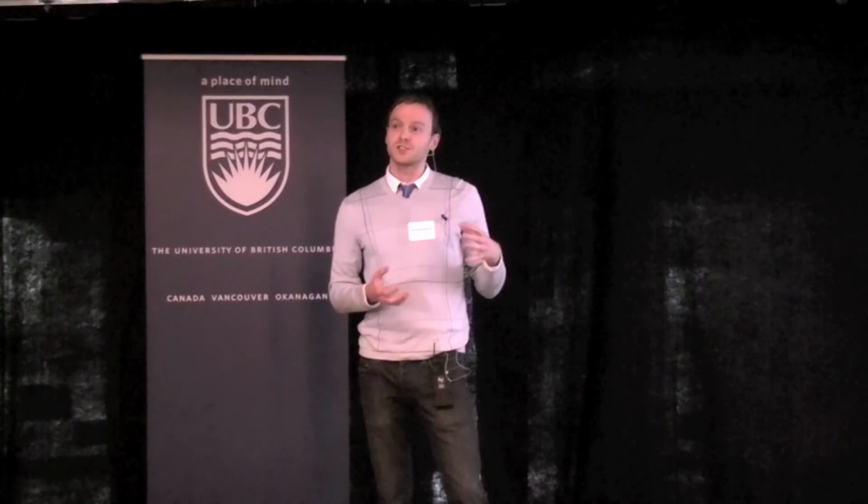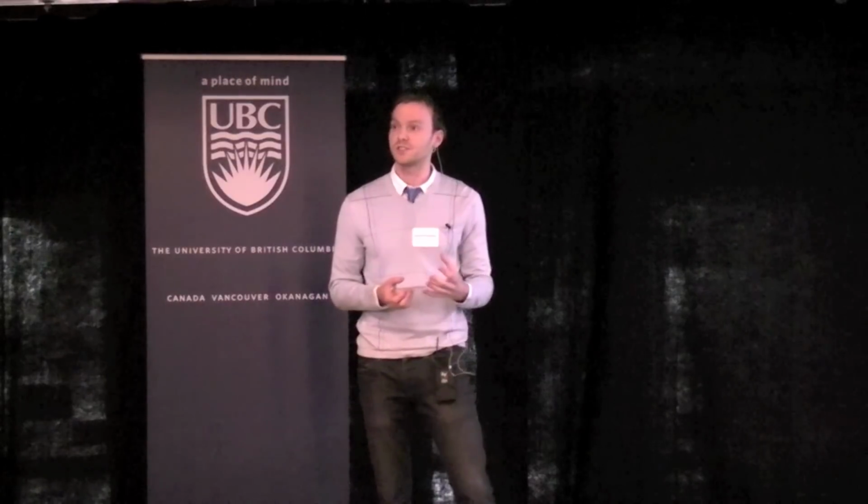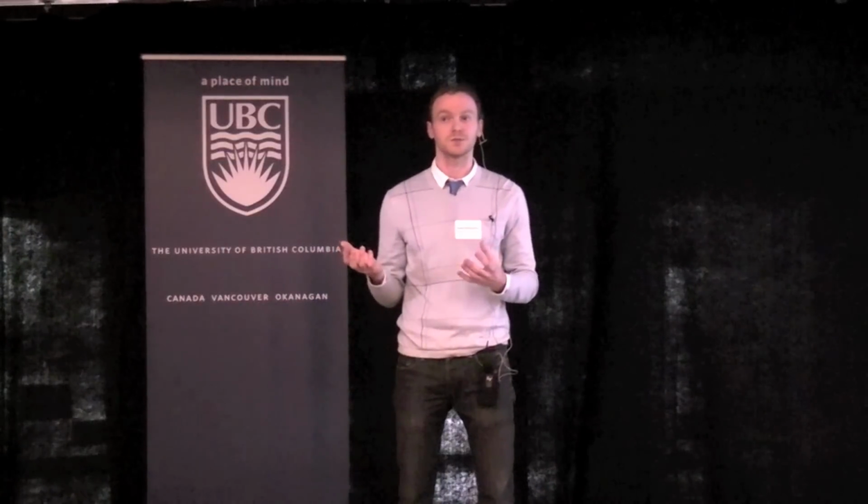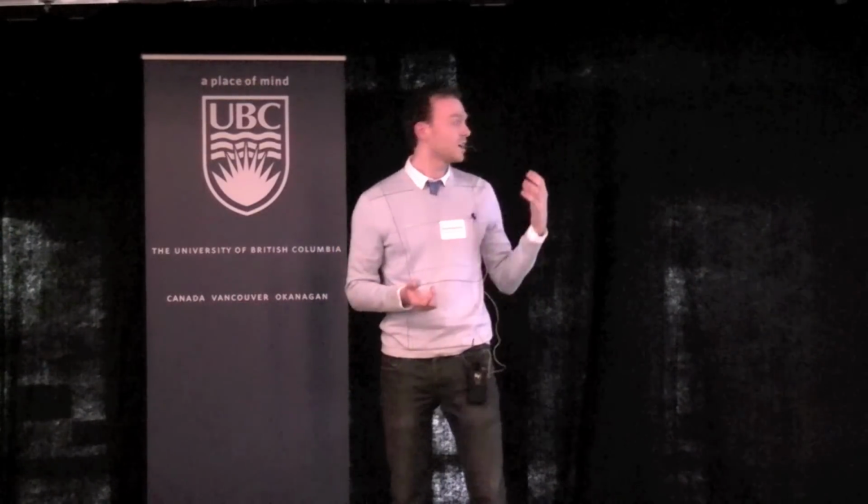The focus of my research is to provide an understanding of this energy use for air filters, and to hopefully improve the energy efficiency for operation in all of our buildings. To do this, I first look at a macro-scale model of filter energy use. This is an analytical method to calculate just how much energy it costs us to run the filtration systems in our buildings.